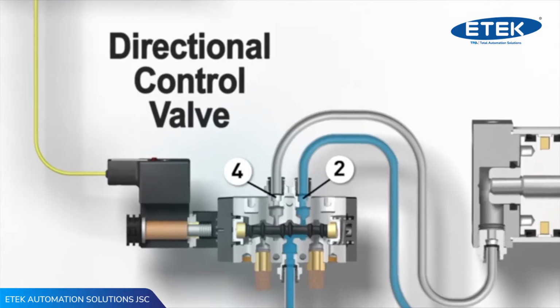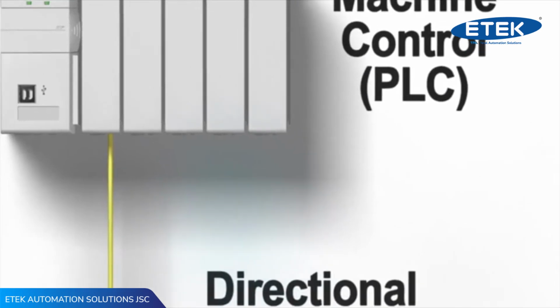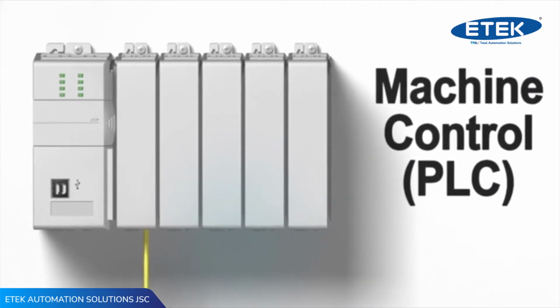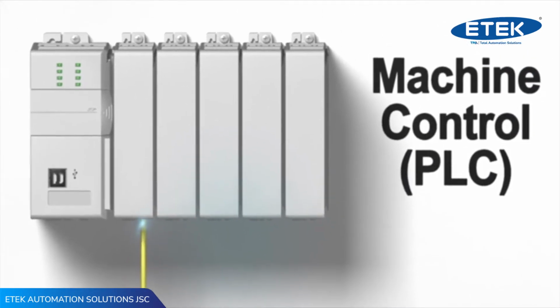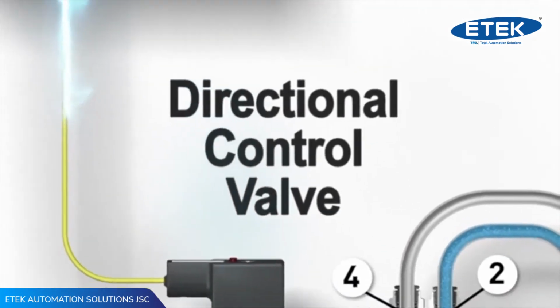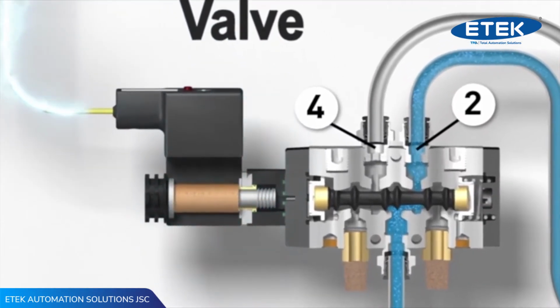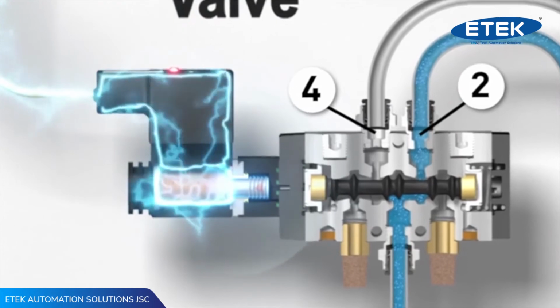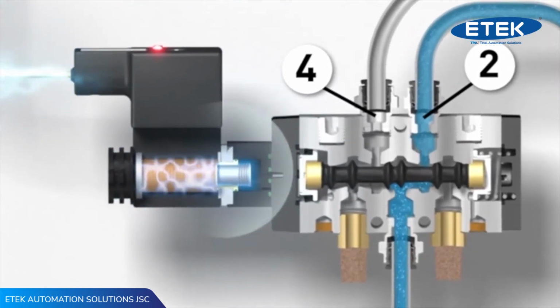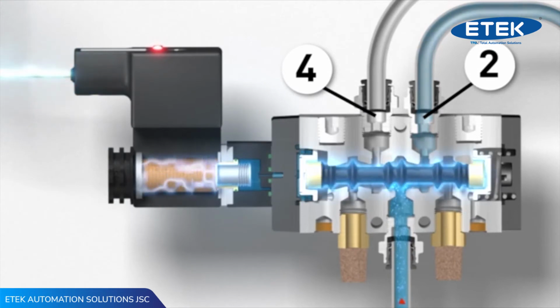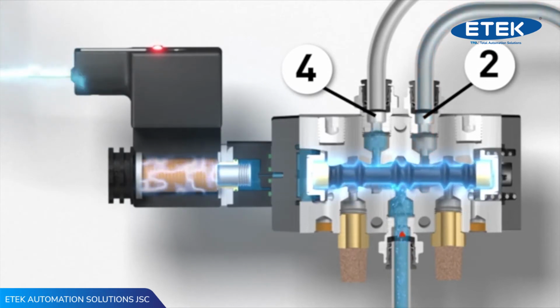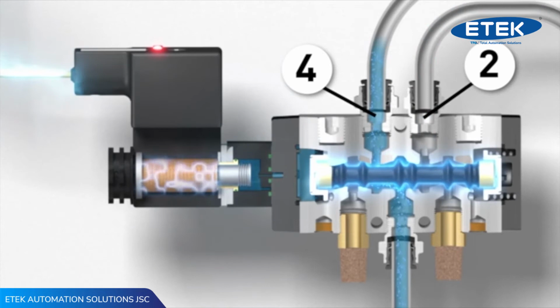In order to change the direction of the air to the number 4 working port, the valve needs to be turned on. In most automated equipment, a PLC, or programmable logic controller, will instruct the valve to shift using an electrical signal. When the signal arrives at a portion of the valve called a solenoid coil, a magnetic field is created that pulls a cylindrical piece called a plunger towards it. When that plunger is unseated, it allows air from inside the valve, known as pilot pressure, to push the spool to the right.